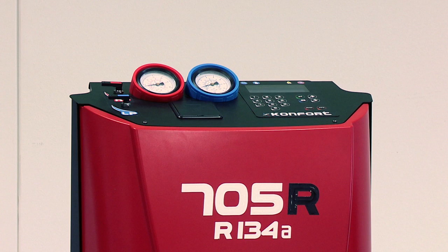This introduction is important to present the main point of this discussion: the wrong practice of removing all the oil from the air conditioning system during the standard maintenance. In fact, in several markets, there is a wrong belief that during standard AC system maintenance, it is better to remove all the oil from the AC system. To do that, the AC equipment users do not only recover refrigerant, but they also flush the entire AC system by means of a push and pull strategy, which consists in flowing refrigerant into the AC system by keeping the compressor of the AC system running.